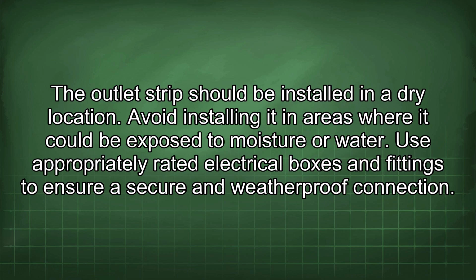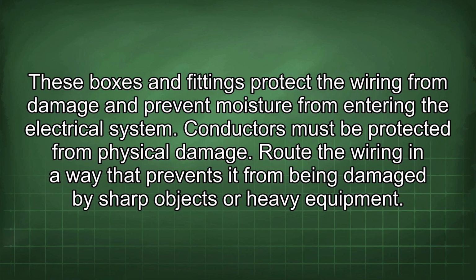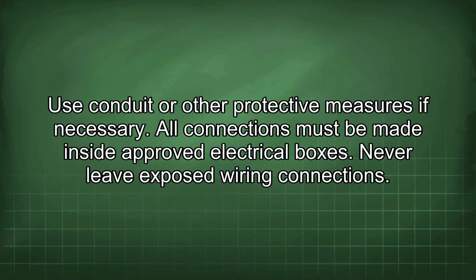Use appropriately rated electrical boxes and fittings to ensure a secure and weatherproof connection. These boxes and fittings protect the wiring from damage and prevent moisture from entering the electrical system. Conductors must be protected from physical damage. Route the wiring in a way that prevents it from being damaged by sharp objects or heavy equipment. Use conduit or other protective measures if necessary.